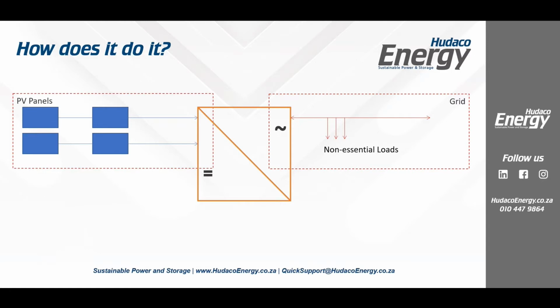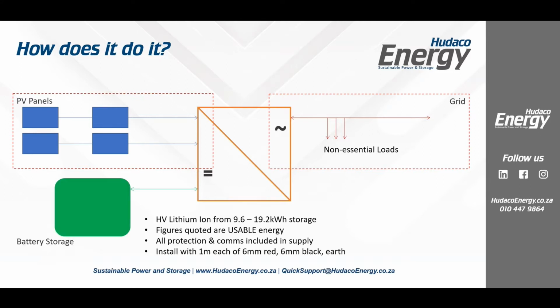The next input we've got is the battery input. It's the battery storage. Again, high voltage lithium ion, and the stacks range anywhere from 9.6 kilowatt hours up to 19.2 kilowatt hours of storage. The units come with a base. You then just stack each cell on top. You put the protection unit in the side, connect up your cables, drop the battery management system on top, which comes in the lid, and you're effectively ready to commission.